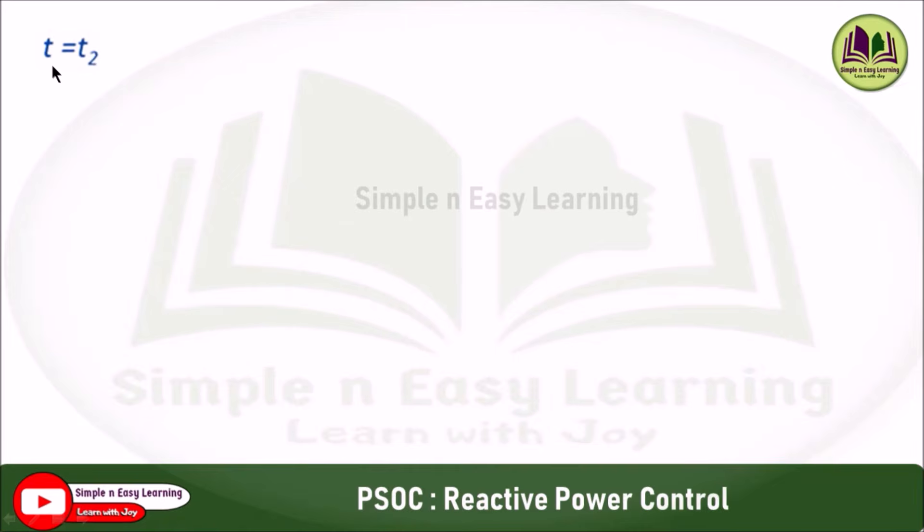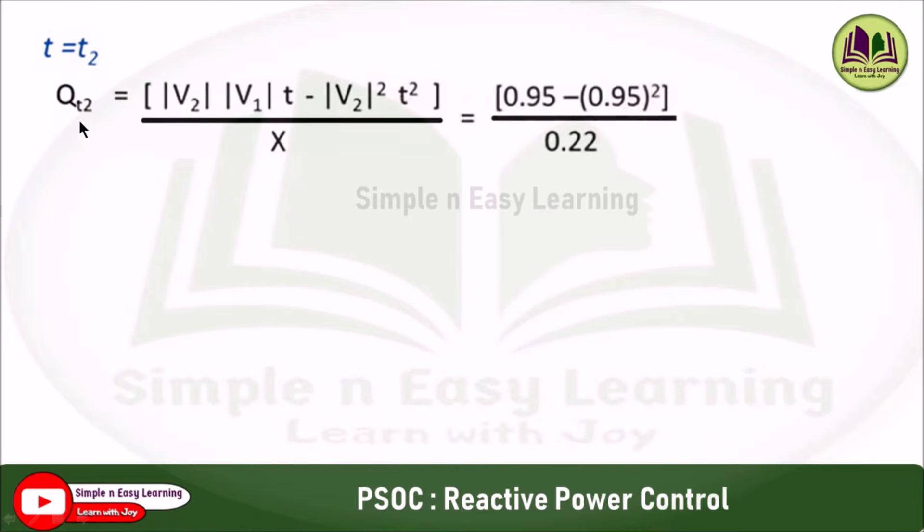Second, for taps T equals T2, apply the formula: V2 times V1 times T minus V2 squared T squared divided by X. T equals 0.95 here, so 0.95 minus 0.95 squared divided by 0.22, that gives 0.2159 per unit.